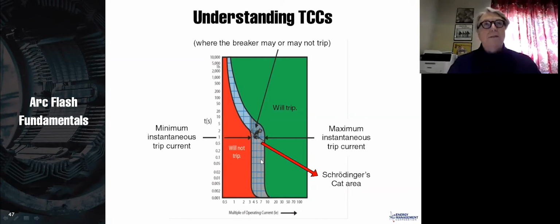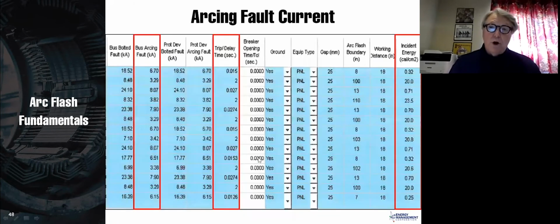And what causes those unknowns? Well, manufacturing variances can cause the unknowns. The temperature at which the breaker or fuse operates, the ambient temperature, could make a difference. The previous loadings on that could make a difference, and so on and so forth. So we don't really know. So how do we look at that area? Generally, when we look at that area from an arc flash point of view, we assume that it is not going to trip because we simply don't know.